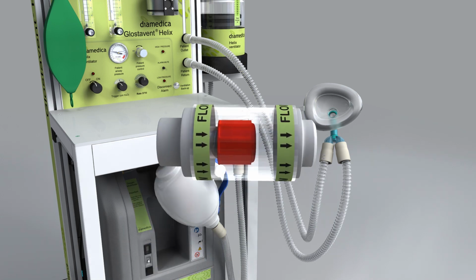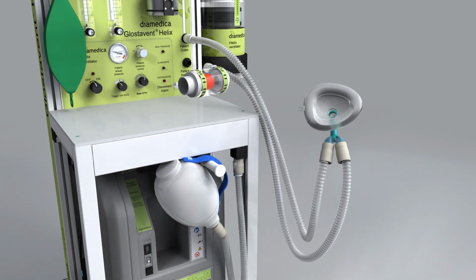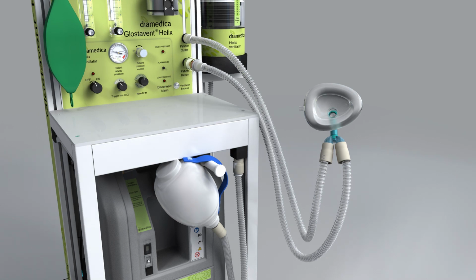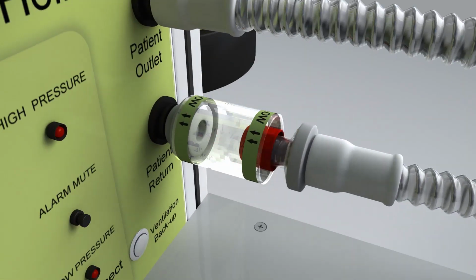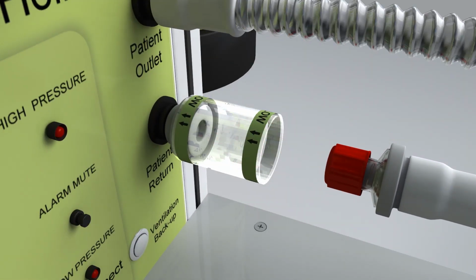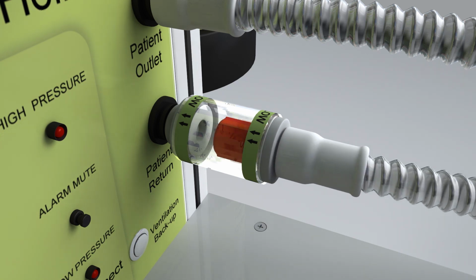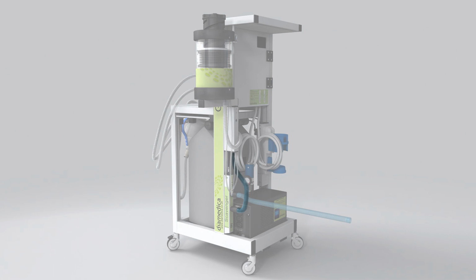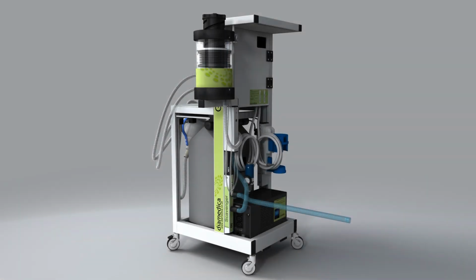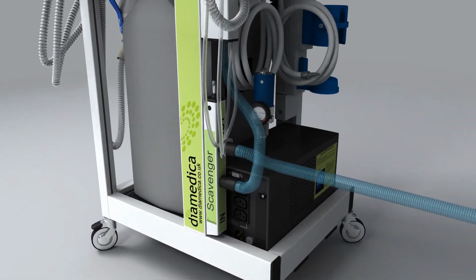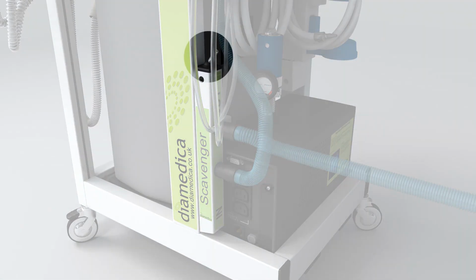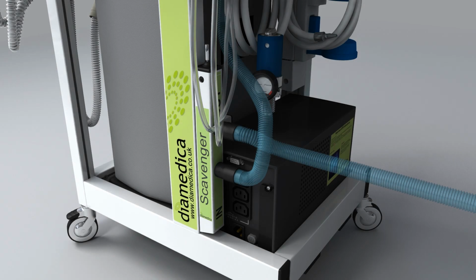The PEEP valve supplied can be fitted to the patient return connection, which can be used from 5 to 20 centimeters of water pressure. This can be adjusted by removing the PEEP valve from the casing and turning clockwise to increase pressure and anti-clockwise to decrease pressure. Waste gases from the expiratory side of the patient valve can be taken through the scavenger tube. The scavenger is located on the back right-hand leg of the machine and is operated by a switch on the top. This operates a fan built into the scavenger to assist in removing the patient's expired gases.